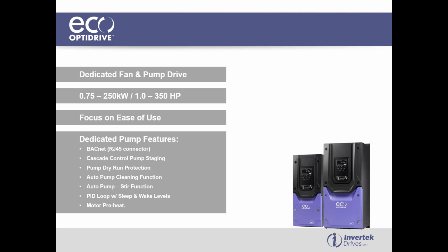when there's no demand on the system, it automatically goes into standby mode, so that it's not burning energy for no reason. Then if it's in that standby mode for a long time, we can use the pump stir function just to stir up the water in the pump, so we don't have problems with sediment settling on the pump impeller. We've also got a motor preheat function available in the drive as well for cold room type applications, so refrigeration, where we can preheat the motor before we start. This is to help stop condensation buildup in the motor, which can be problematic.